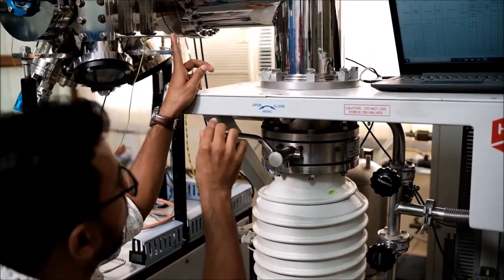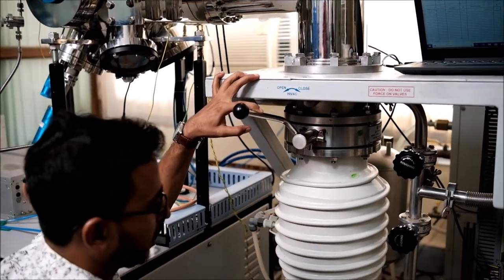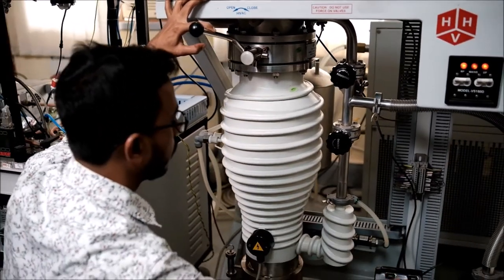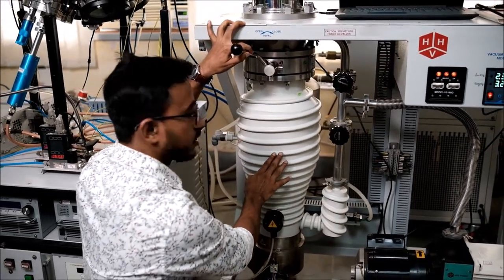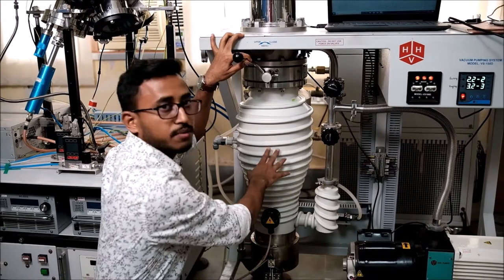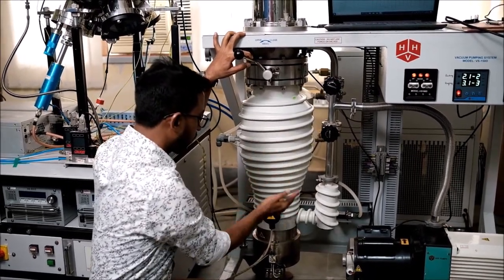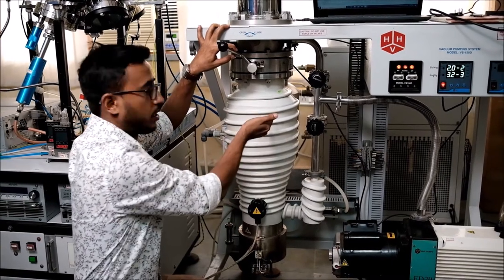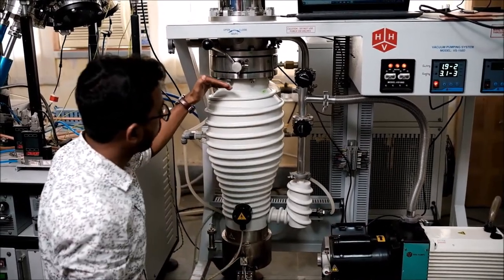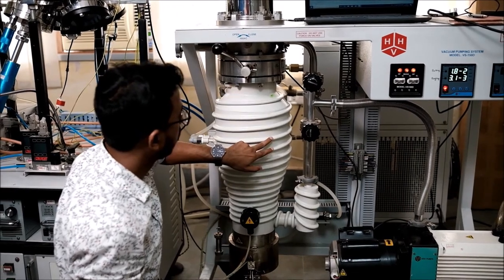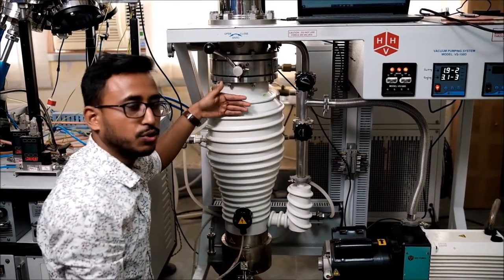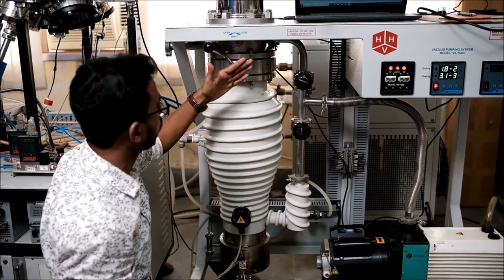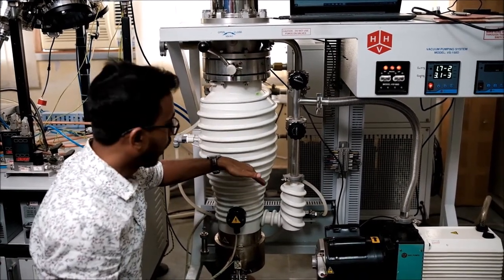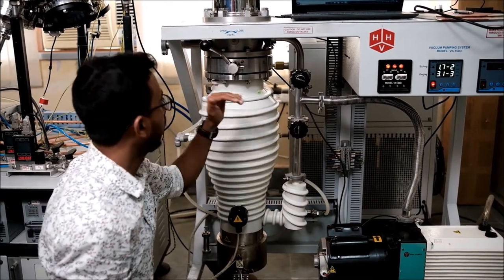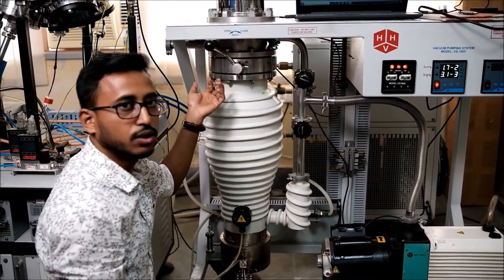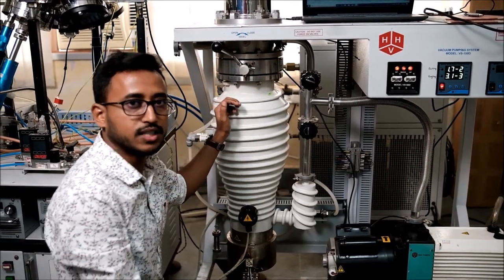So this way now the chamber is connected to the diffusion pump, and at the back of the diffusion pump this rotary pump is connected. Now inside the diffusion pump chamber, the mechanical structure is maintained in such a way that it converts this oil vapor into a jet, and when the jet enters from center to the wall, it transfers its momentum to the air molecules, and thus the air molecules from the top part come down to the bottom part, and the rotary pump takes out the air molecules, and thus the pressure gets down, and it can do this till it reaches 10 to the power minus 6 millibar of pressure.